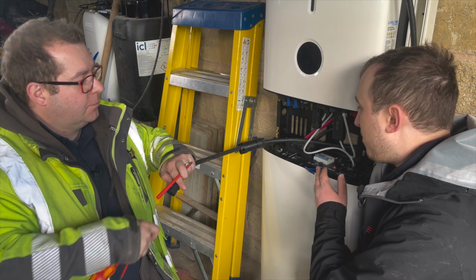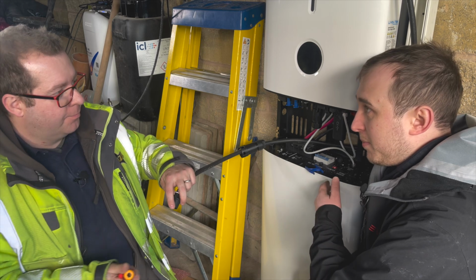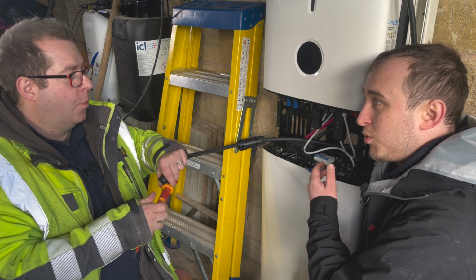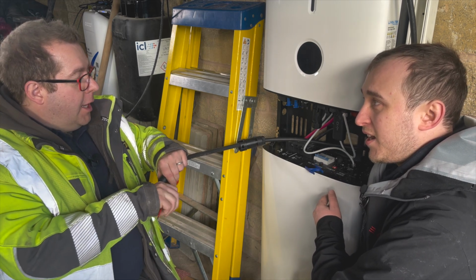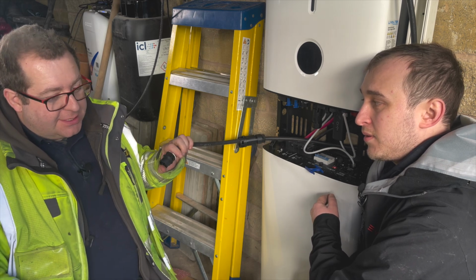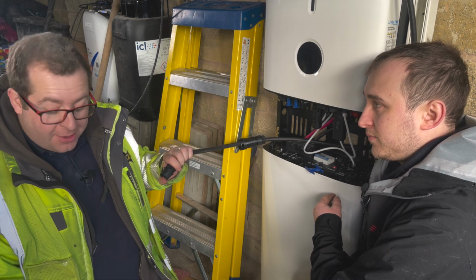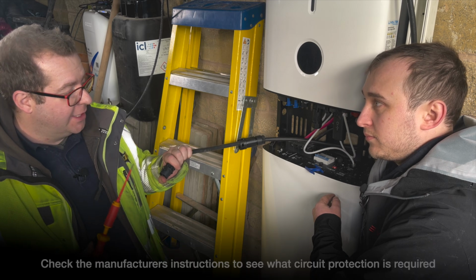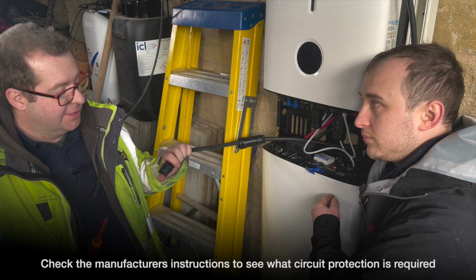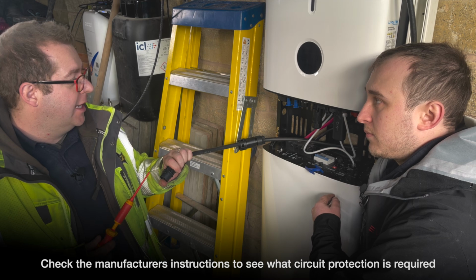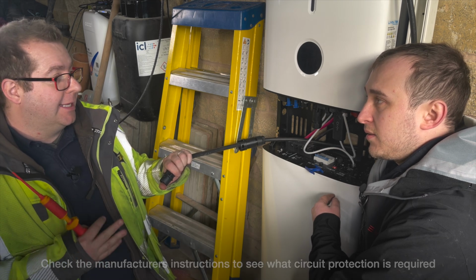In this situation we're not wiring up the EPS, but if we were, would you have a separate consumer unit for the EPS side? Yes, I'd have a separate consumer unit. I need to check the regulations for what's needed in terms of RCD protection, and it would need its own TT earth as well.